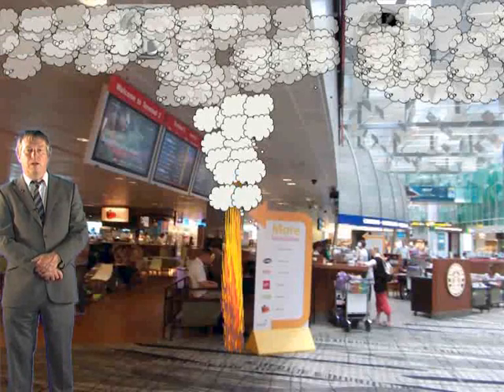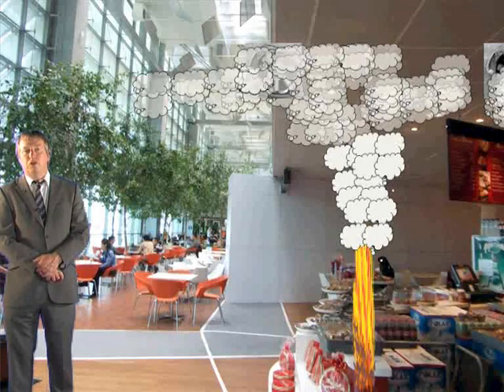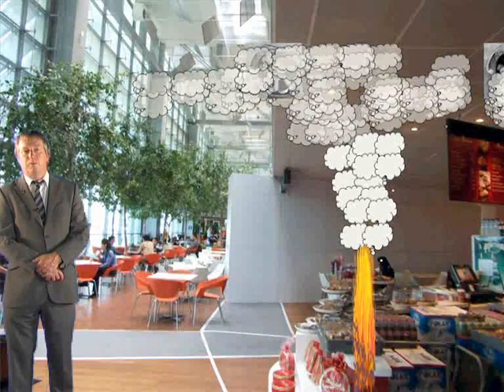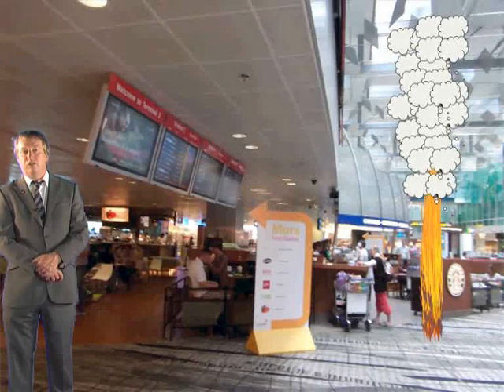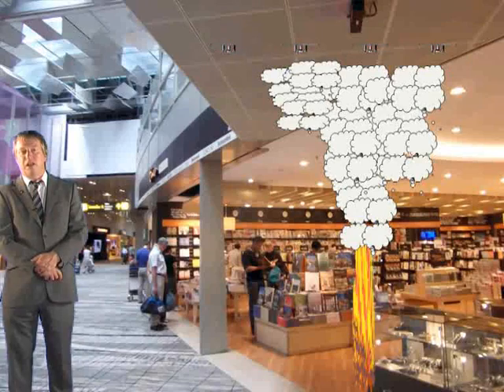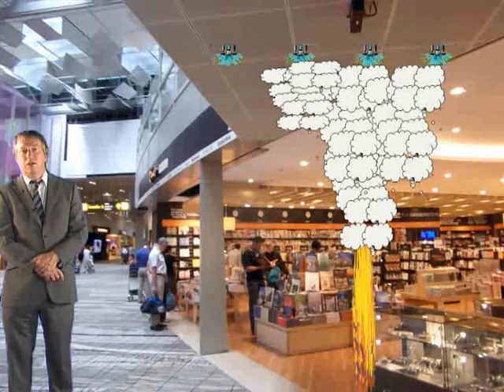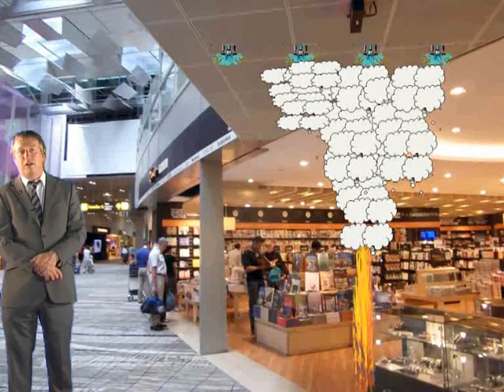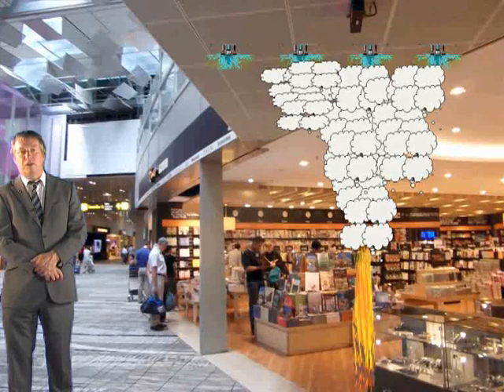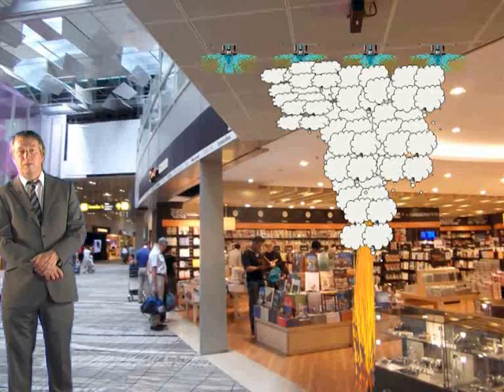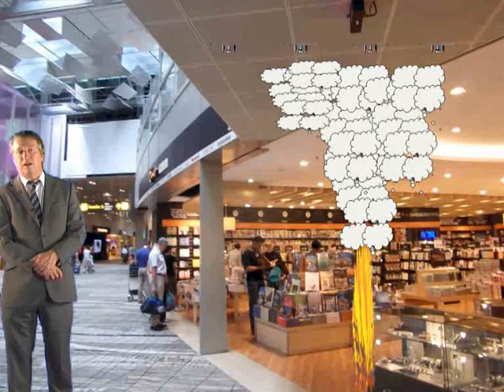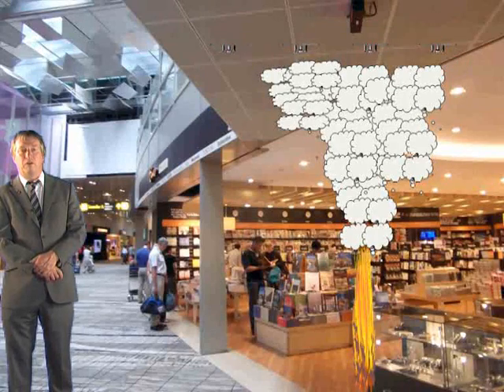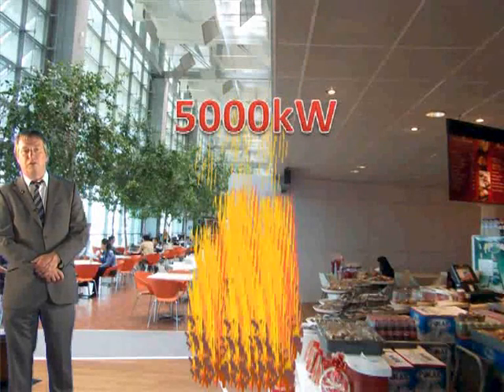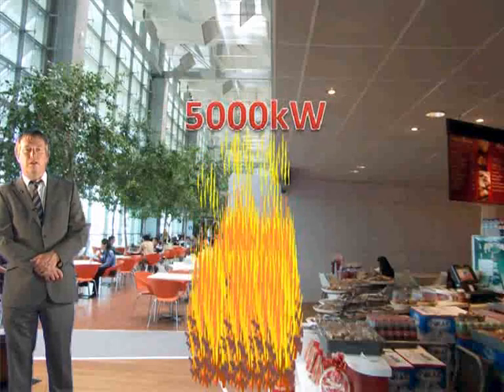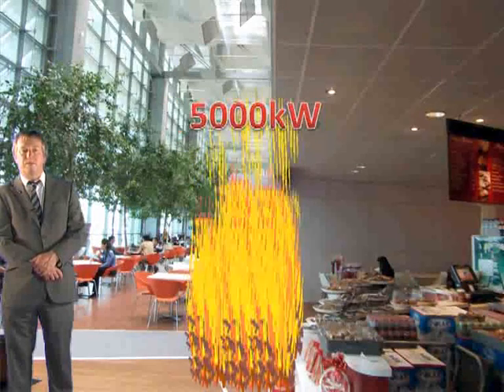There may be a fire in one of the shops in a mall, and there could be a store located directly in the atrium, and there could be a covered cabin with sprinkler protection. In this case, you may have to analyse all the design fires to determine the highest mass flow rate of smoke, and the ventilation system must cope with this, as well as taking into account the temperature of the smoke layer as well. Once you've identified the design fire size, you need to determine the convection portion of this.